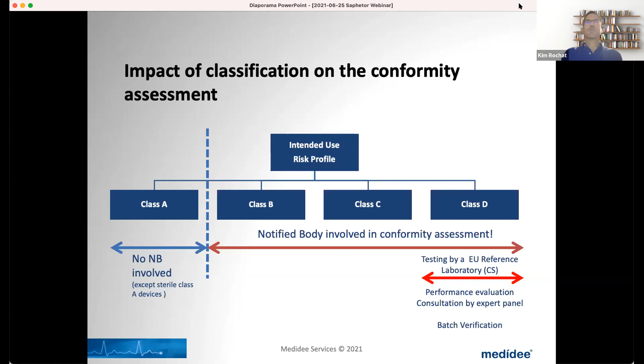One of the other important points, as mentioned with the notion of data, is that every in vitro diagnostic device placed on the market will have to demonstrate safety and performance, and that will be through three main parameters. The first is a demonstration of the scientific validity. So basically, when I'm using an analyte to make a judgment or a diagnostic, is there a real link between the parameters? Then the analytical performance will have to be validated. So basically, am I really able to measure this analyte in terms of specificity and sensitivity? So basically the technical performance of the product.